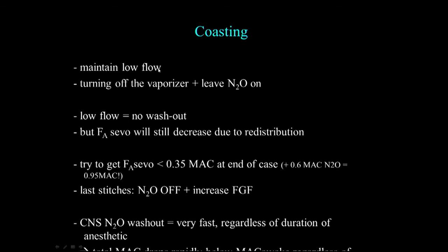You maintain a low flow, but you switch off the vaporizer, but leave the nitrous oxide on. Andre talked about this last year. Because the flow is low, there is no washout, but the end-tidal sevoflurane will still decrease due to redistribution. And what you want to get is, towards the end, an end-expired sevoflurane concentration of slightly lower than 0.35 MAC. Remember, together with the nitrous oxide, that is still 0.95 MAC.